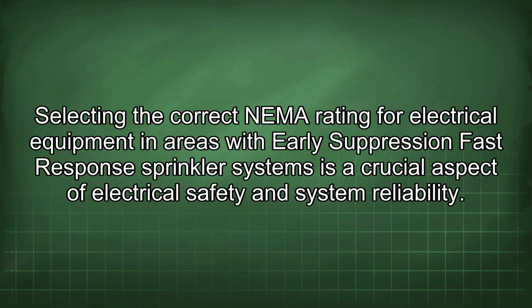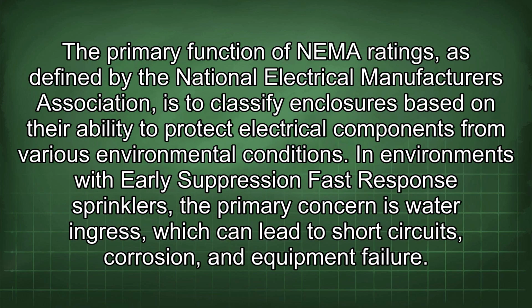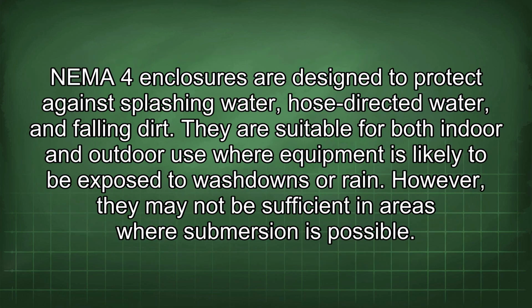Selecting the correct NEMA rating for electrical equipment in areas with early suppression fast response sprinkler systems is a crucial aspect of electrical safety and system reliability. The primary function of NEMA ratings, as defined by the National Electrical Manufacturers Association, is to classify enclosures based on their ability to protect electrical components from various environmental conditions. In environments with early suppression fast response sprinklers, the primary concern is water ingress, which can lead to short circuits, corrosion, and equipment failure. NEMA 4 enclosures are designed to protect against splashing water, hose-directed water, and falling dirt.